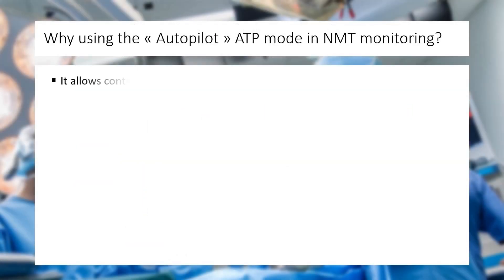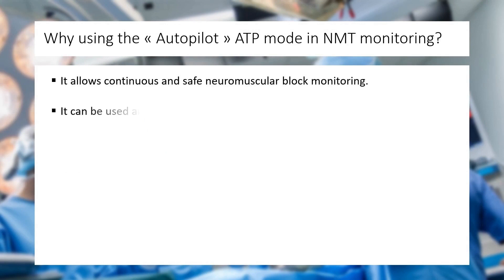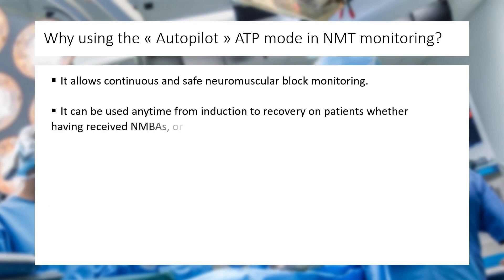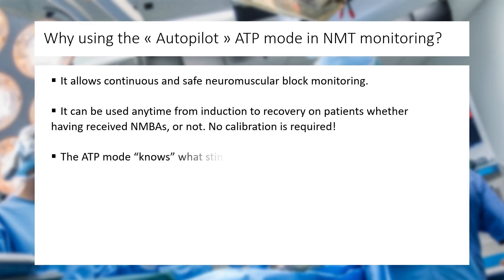Using the autopilot ATP mode will allow continuous safe block monitoring. It can be used any time from induction to recovery on paralysed patients or not. TOF scan does not require calibration. The ATP mode pilots the choice of TOF or PTC stimuli according to the level of patient blockade.